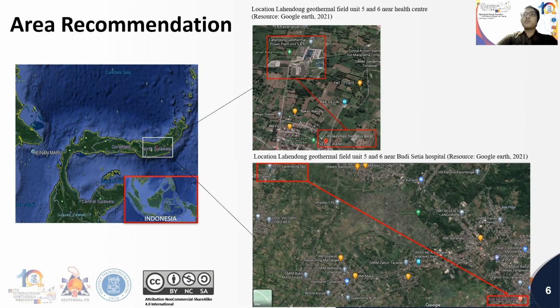The cascading system only uses brine from PLTP Lahendong Unit 5, and based on the map, the distance from the geothermal field to the health center following the injection pipe is 1.29 km, and to the hospital is 6.5 km. The location of the source is very important to choose, needing to be close to the health center or hospital so that the heat can be used efficiently.